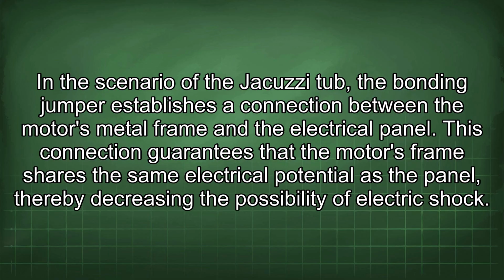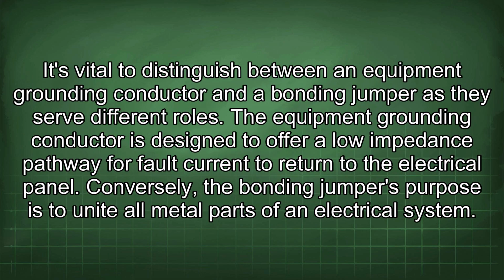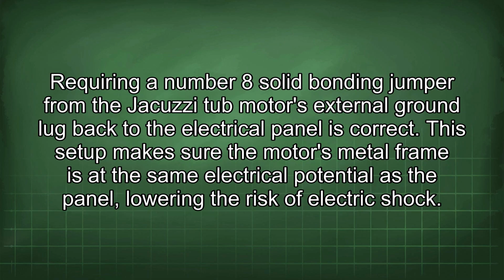possibility of electric shock. It's vital to distinguish between an equipment grounding conductor and a bonding jumper, as they serve different roles. The equipment grounding conductor is designed to offer a low impedance pathway for fault current to return to the electrical panel. Conversely, the bonding jumper's purpose is to unite all metal parts of an electrical system. Requiring a number 8 solid bonding jumper from the Jacuzzi tub motor's external ground lug back to the electrical panel is correct. This setup makes sure the motor's metal frame is at the same electrical potential as the panel, lowering the risk of electric shock.